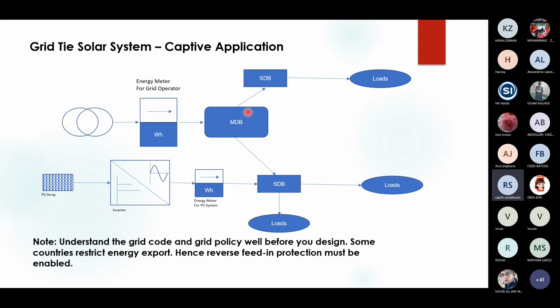Here is the basic connection diagram of a grid-tie solar system for captive applications. Let me explain how captive and independent power plants work. Captive means whatever energy you produce, you use in your own loads. Here you see a PV array connected to an inverter, converting the direct wave into a sinusoidal wave. Then you measure how much energy you're getting from the PV system and pump it into a sub-distribution board, or even route it to the main distribution board—it doesn't matter—and it's absorbed by the loads.